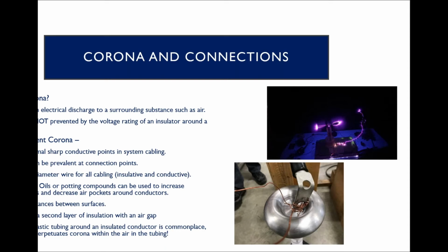So a few of the things to note on how to prevent corona is to really ensure that you don't have sharp conductive points in your cabling. So these can be really prevalent at points of connection. They can also be really prevalent if your wiring is damaged in any way. One of the goals will be to really use larger diameter wire for all of your cabling, because it's not really the rating of the insulator, it's the diameter of the cable which smooths out all of those sharp points. A typical cable will be a stranded cable, where each of those strands will then be a sharp point. But if you increase the outer diameter, you have fewer sharp points to help keep that down.